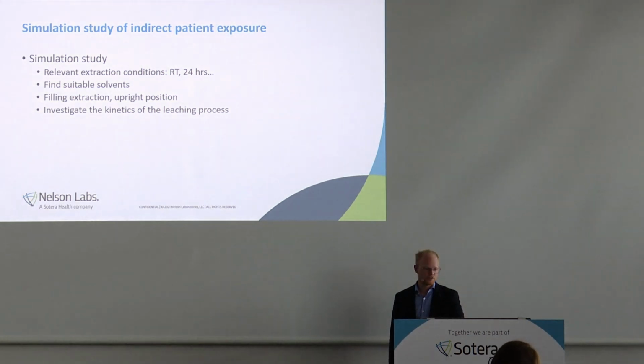What is the use of such feeding bags? Yeah, room temperature, yes. Maybe 37 degrees C if children are in the population and the feeding solution needs to be heated a little bit. But yeah, 37 to 40 degrees C can be the maximum, not 50. 24 hours is the maximum time because, for instance, the IFU says replace or use a different bag every day.